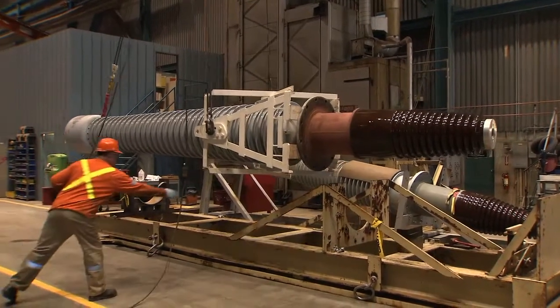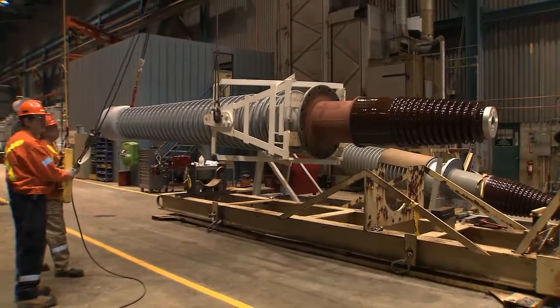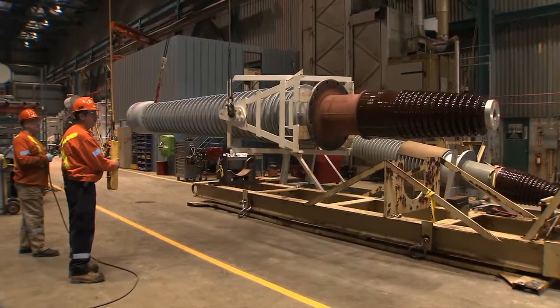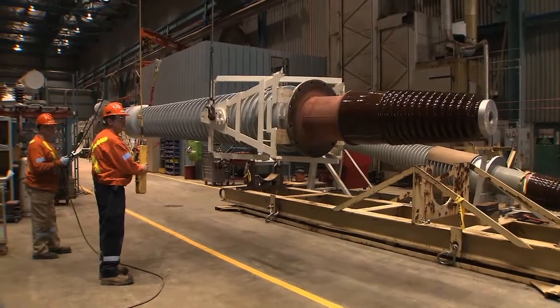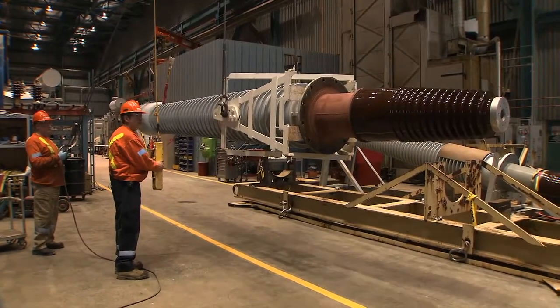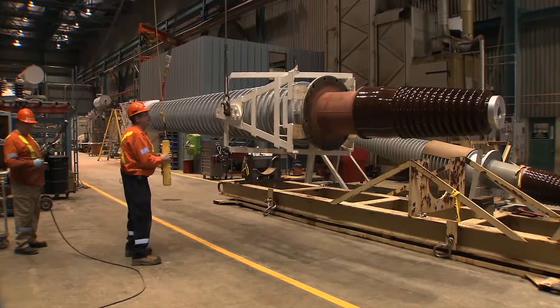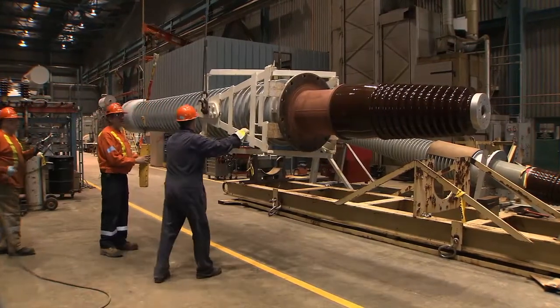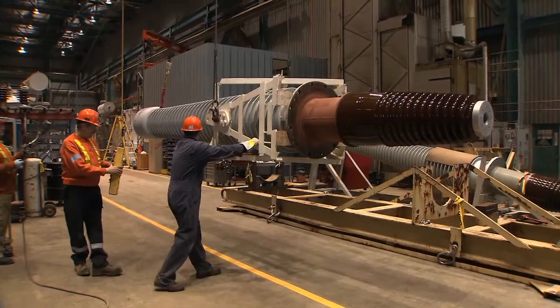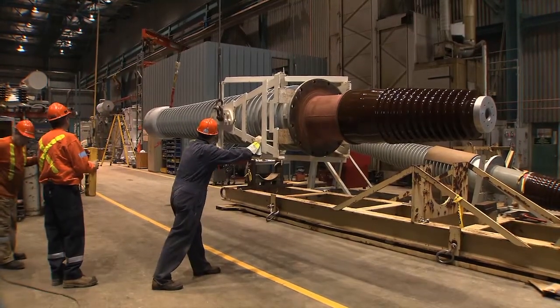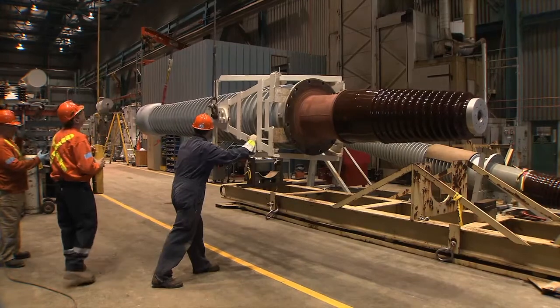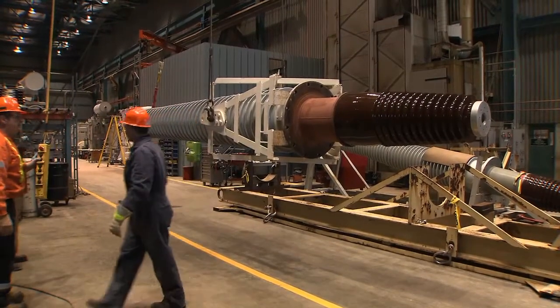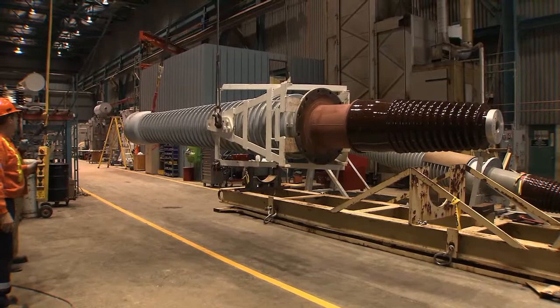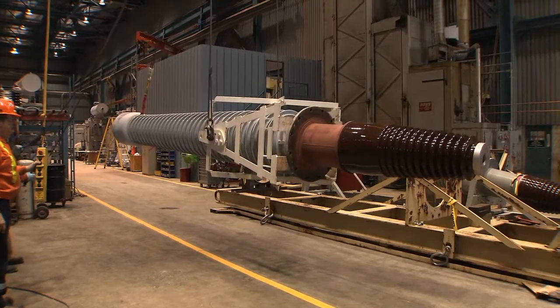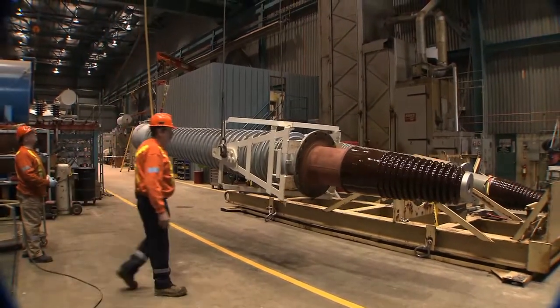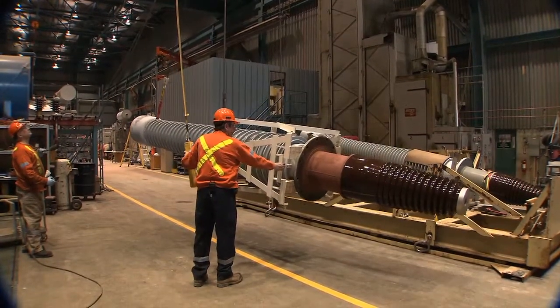When the bushing is above the transport carrier, move it eastbound to a position about 4 feet above the yellow line on the concrete floor. Begin tilting the bushing by lowering the bottom end, where the lifting jig is attached, and raising the top end, where the sling is choked. Now the actual tilting is going to start taking place. Okay? So Graham, if you want, you can start raising your end. Yeah, I'll start taking it down at the bottom.